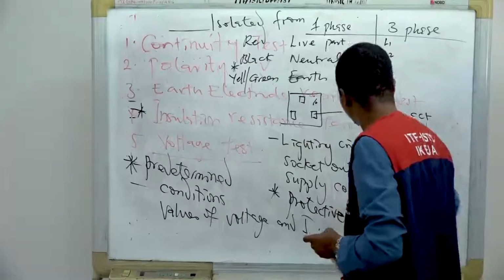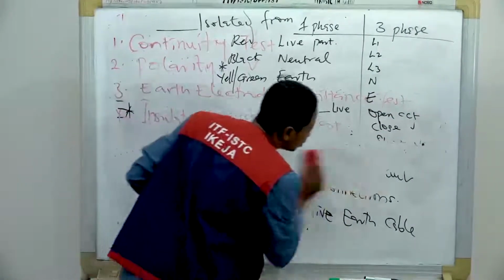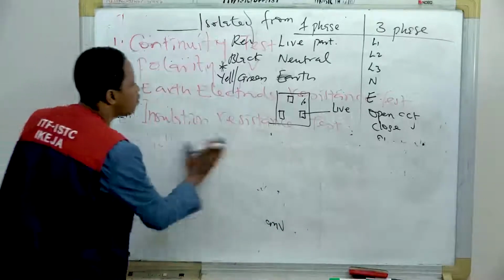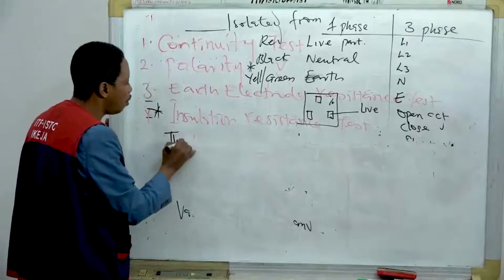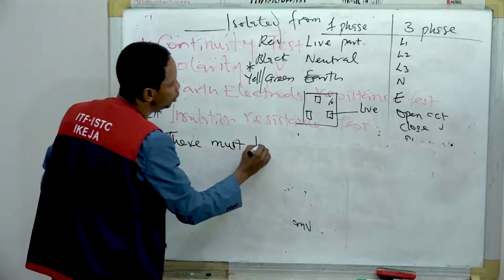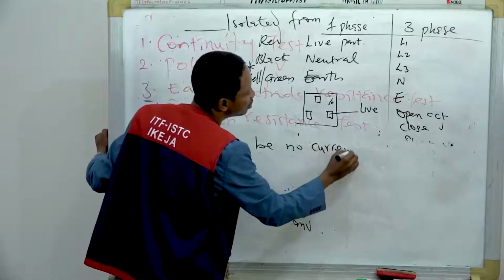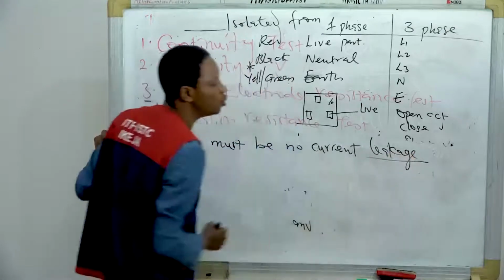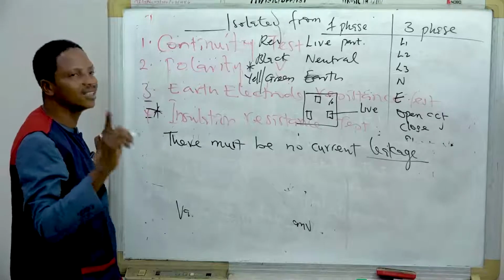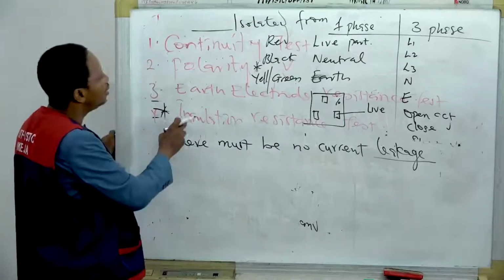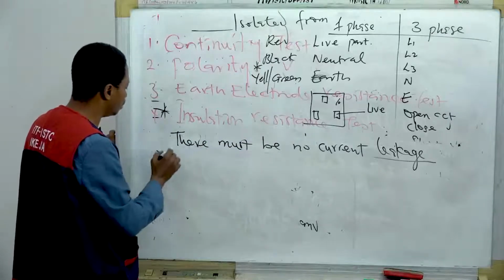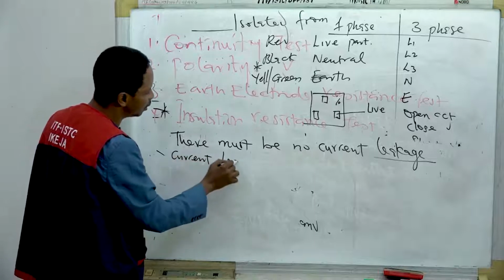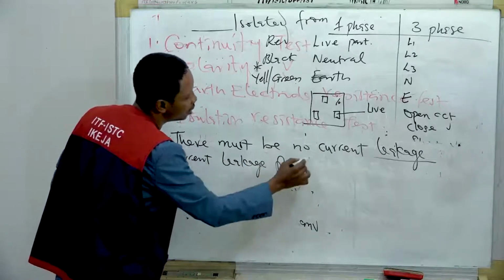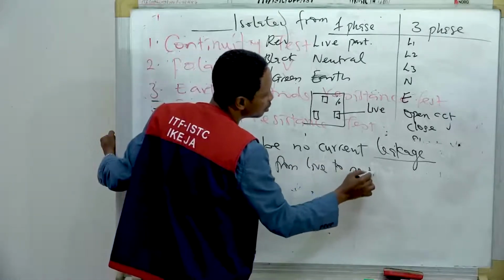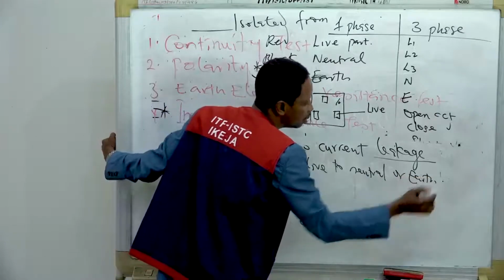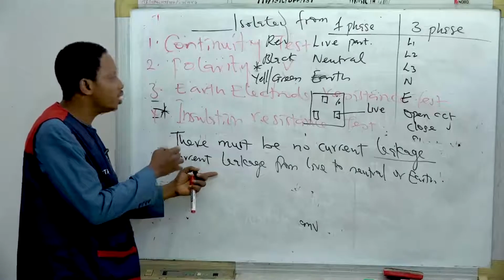Insulation resistance test. For insulation resistance test, what are we looking for? There must be no current leakage in the circuit. No current leakage. There must be no what? Current leakage in the circuit. So, carrying out insulation resistance test is to confirm, one, current leakage from live to neutral or earth.